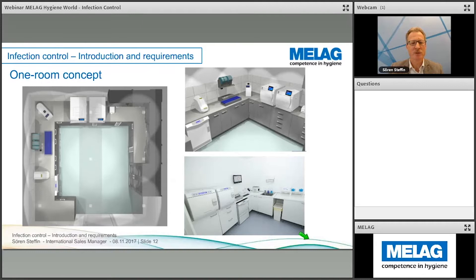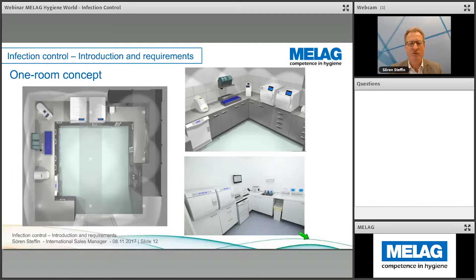Here we see some planning station pictures — a top view showing a square room where we can arrange all the different things from left to right, or in a corner situation. Below, we see a live view of how it is arranged in a small dental clinic, nicely with two sterilizers, a washer disinfector, and all the documentation systems. The practical view does not show a big area — we really can do it on small surfaces with highly integrated, high results.